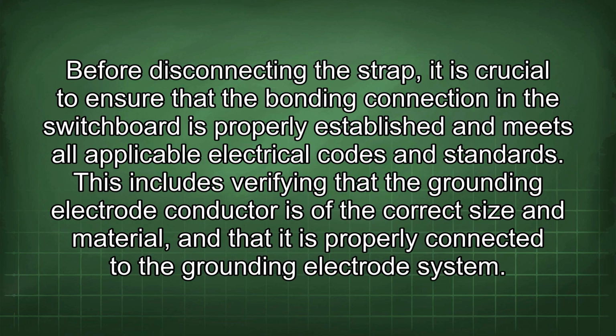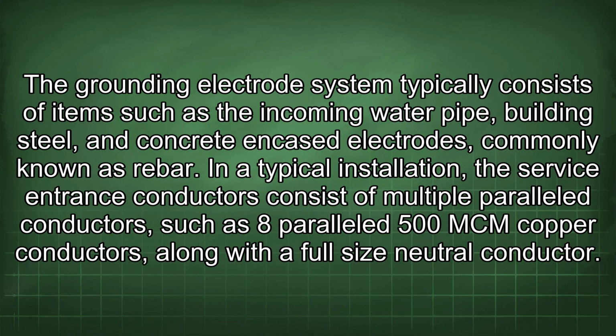Before disconnecting the strap, it is crucial to ensure that the bonding connection in the switchboard is properly established and meets all applicable electrical codes and standards. This includes verifying that the grounding electrode conductor is of the correct size and material, and that it is properly connected to the grounding electrode system. The grounding electrode system typically consists of items such as the incoming water pipe, building steel, and concrete encased electrodes, commonly known as rebar. In a typical installation, the service entrance conductors consist of multiple paralleled conductors, such as 8 paralleled 500 MCM copper conductors, along with a full-size neutral conductor.